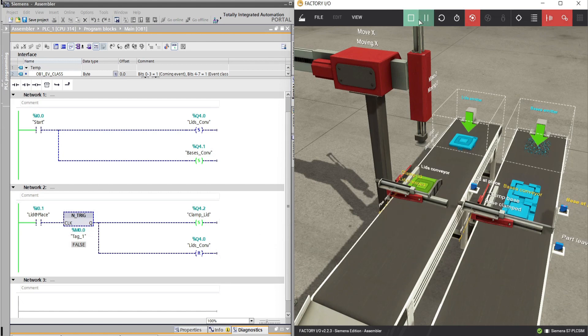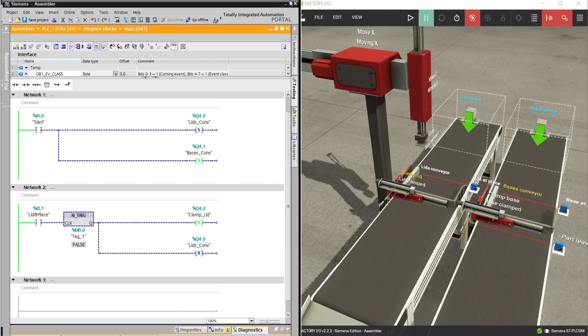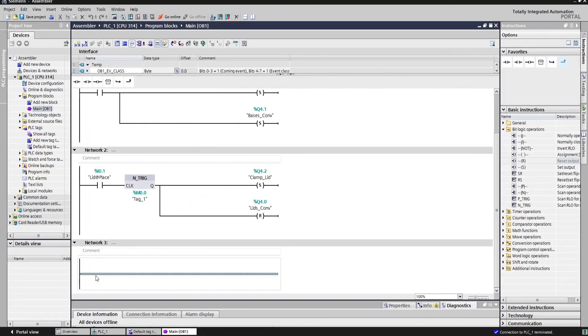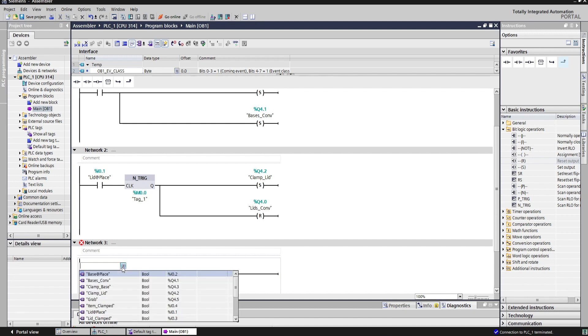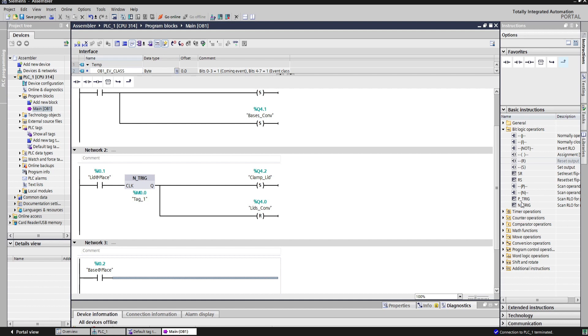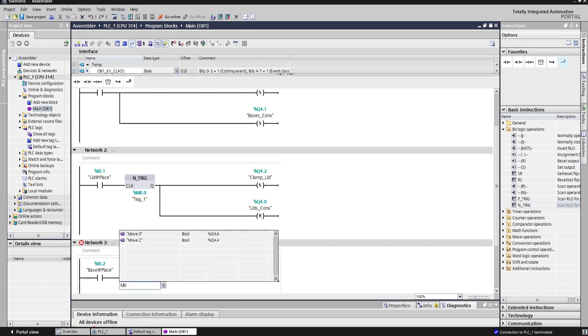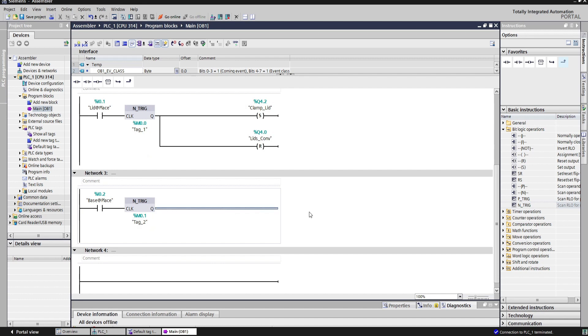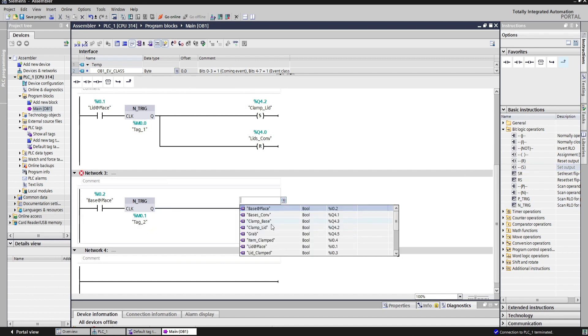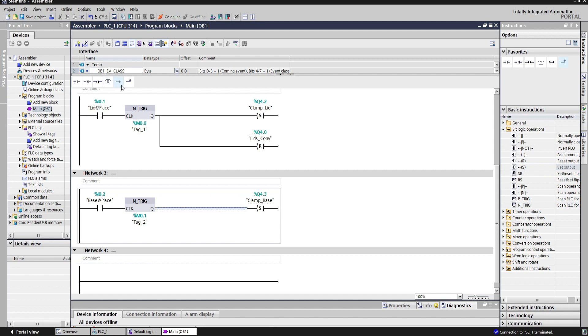Let's continue the programming — the same approach will be used for the base product conveyor. For network 3, let's add an open contact and address it as base at place, followed by an N_TRIG function addressed as M0.1. For the output, let's add a set function for clamp base and a reset function for base conveyor.